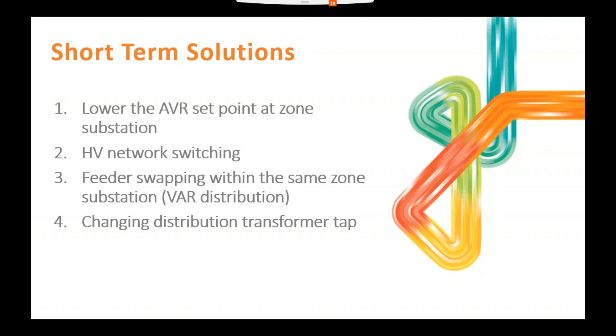Also changing the distribution transformer taps is problematic, because you might change them in summer for one condition with air cons being on at night, and then in spring and autumn with sunny days and lots of solar and reverse power, you'd have to send crews out to change the transformer taps again. That's not a position you want to be in long term at all.